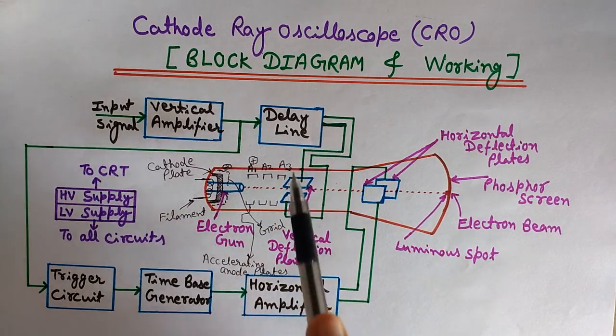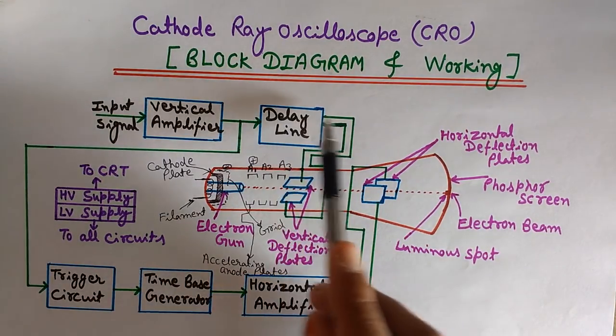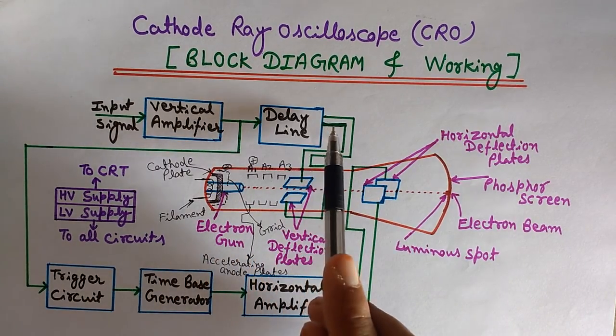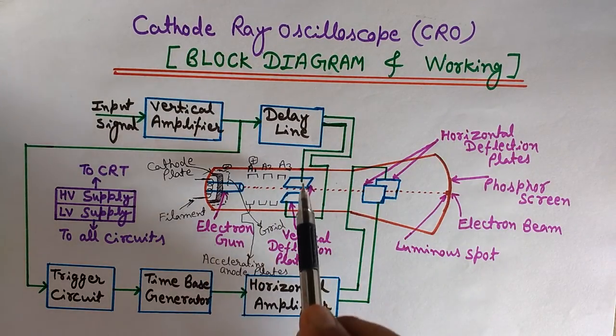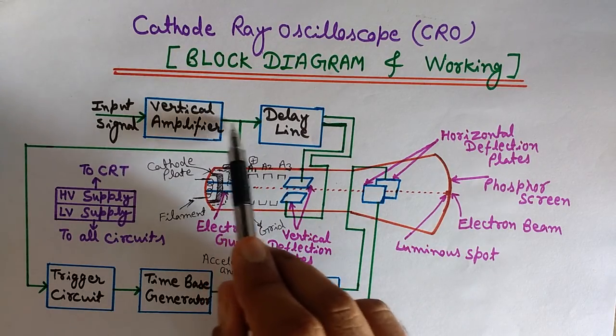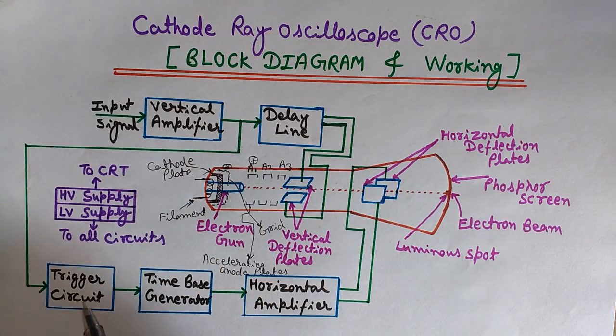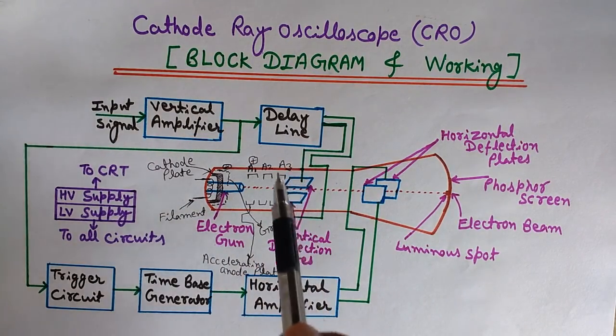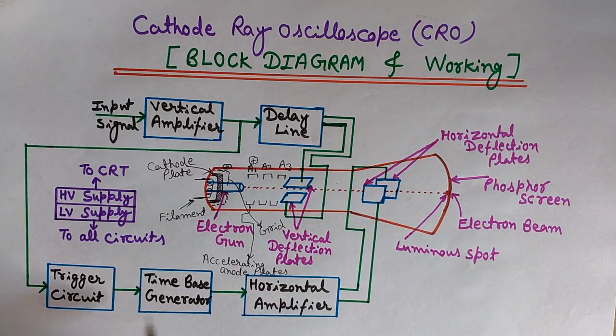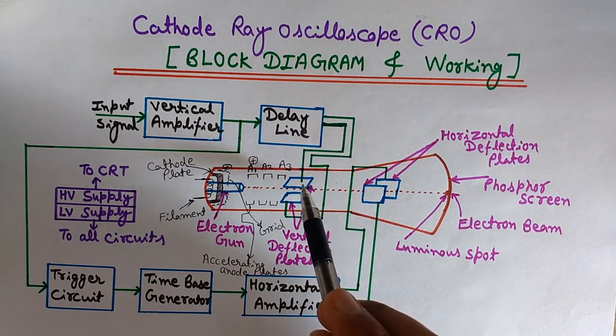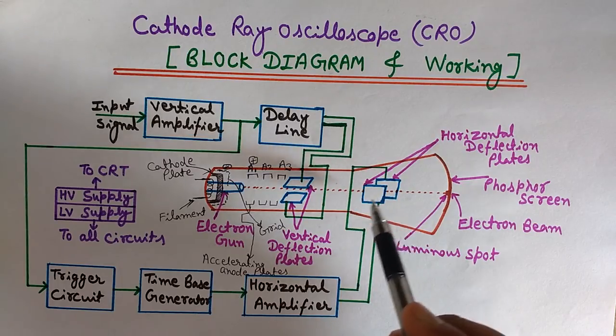A delay line is used here. The output of the vertical amplifier goes to two places: one part goes to this delay line — we do not apply it directly to the vertical deflection plate, we use a delay line first. The other part of the vertical amplifier's output goes to the trigger circuit. The purpose of the delay line is to produce a delay equal to that offered by the trigger circuit and time base generator, because we want the signal to reach both deflection plates at the same time.